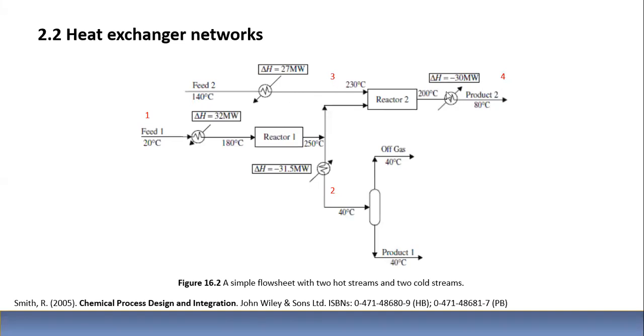Stream number 4 is coming from 200 to 80. So it's giving up heat to the tune of minus 30 megawatts. So if you add minus 30 to minus 31.5, you have minus 61.5 megawatts that you need to absorb by using a cooling tower. So by now, your cooling tower has grown, and you need a humongous cooling tower to do this service. And also, you need a very big, or a series of, boilers to produce the many pounds per hour of live steam at a given saturated pressure to achieve this, almost 60 megawatts of energy in the form of live steam to be input into the process. So this is going to be a very expensive process, to say the least.